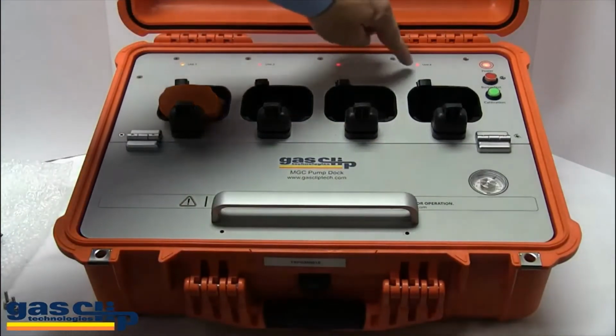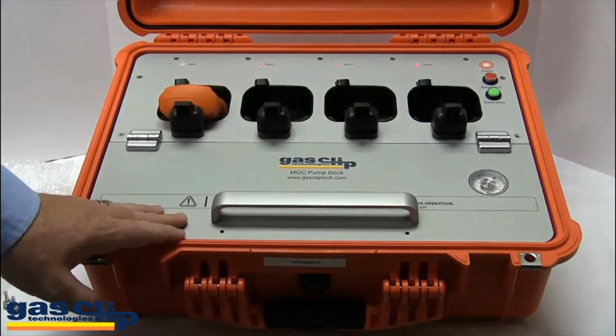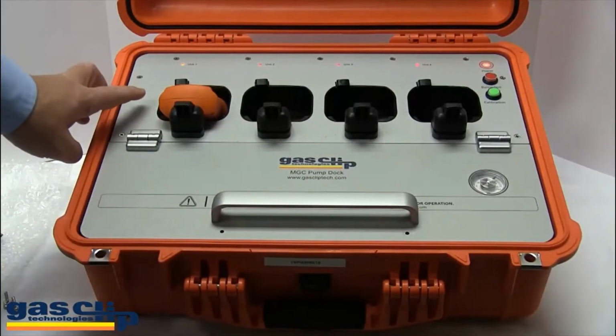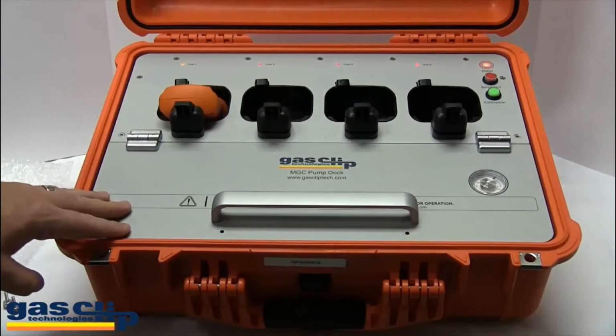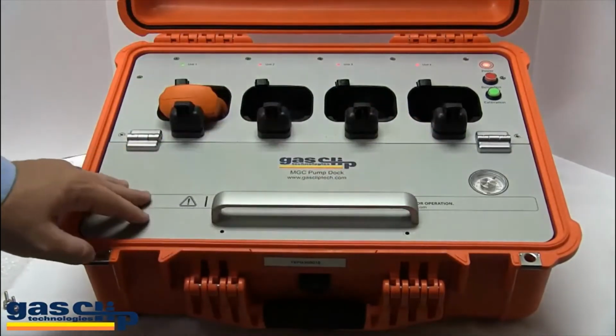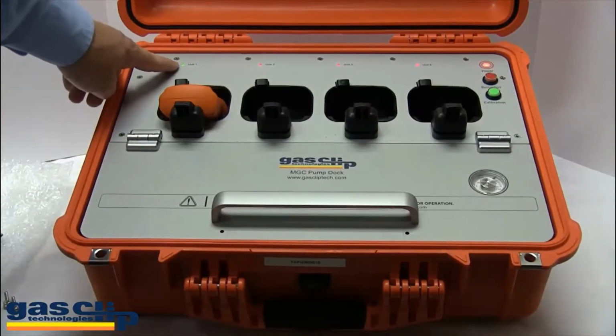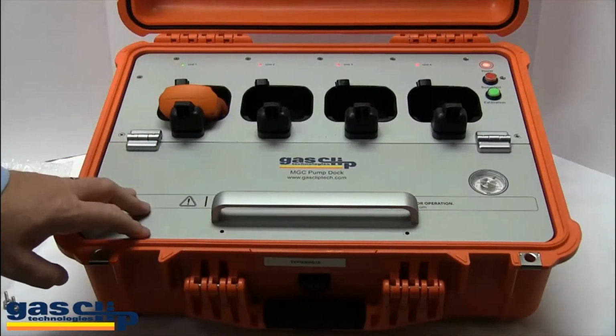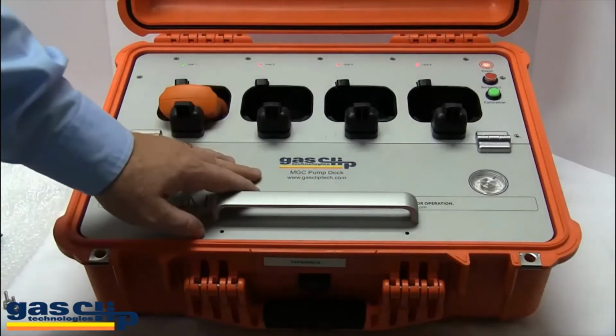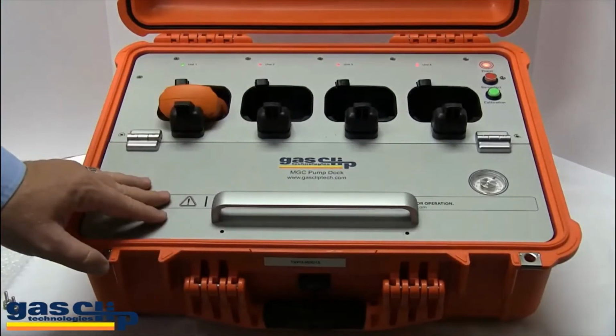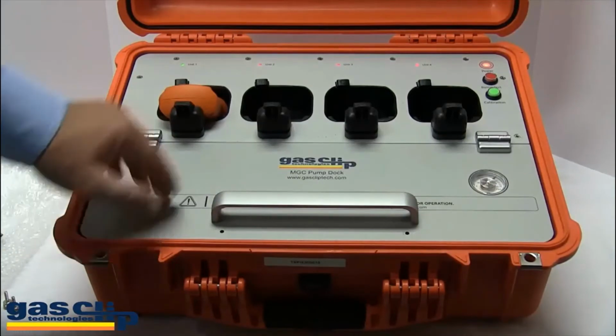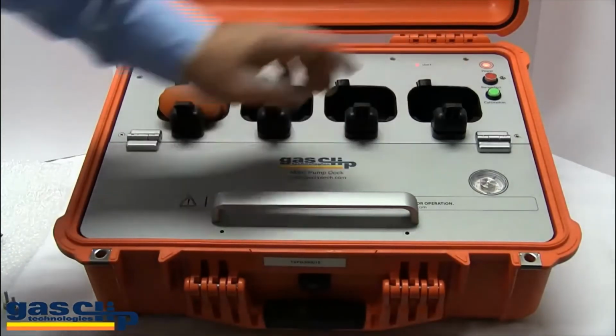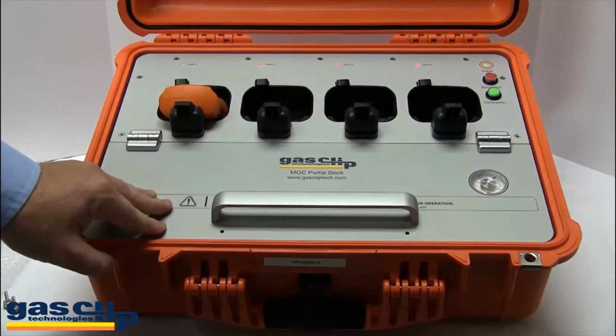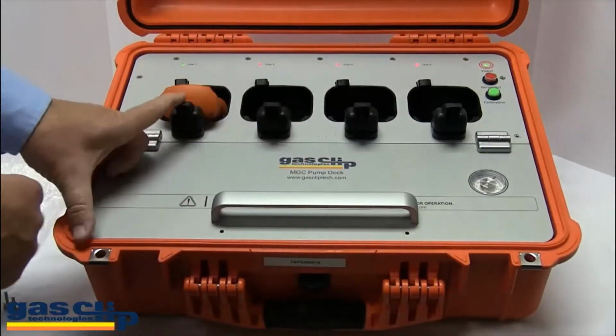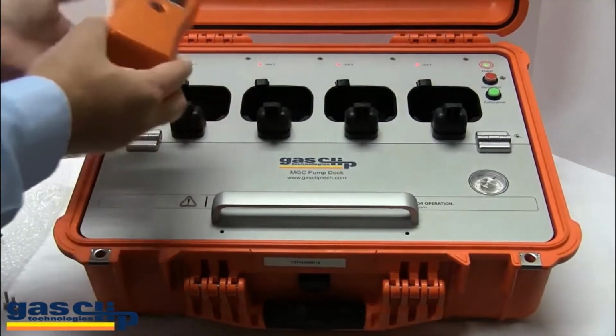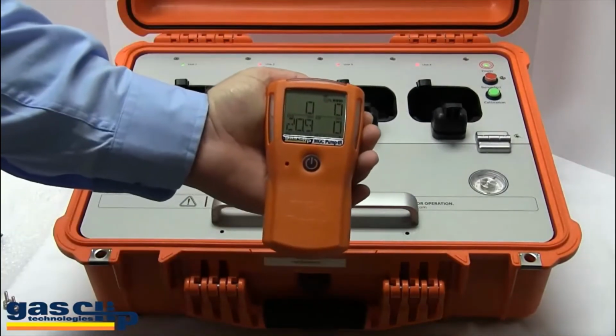Notice that these lights turn red because there are no monitors in the bays themselves. Now gas is being applied to bay 1 since that is the one with the monitor in it. If there were 4 monitors, gas would be applied to all 4 bays. This light has already turned green. Now this is in what we call a purge function. This dock is actually applying fresh air to the monitor to get the sensor readings back down close to zero. As soon as this light turns green, the monitors will be ready for use. Light is green, press down on the handle and remove the monitor. It is now ready to use.